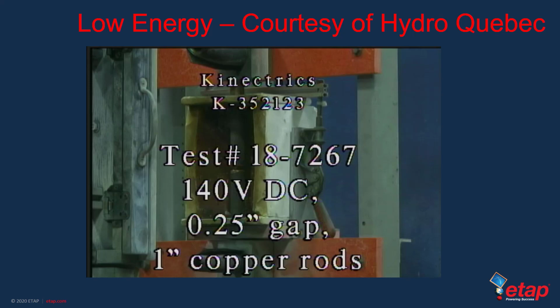The first test is for a 7.8 kiloamp available DC short circuit current system. The initial gap in this system is 6 millimeters, although of course the gap will grow depending on the erosion rate of the copper butted electrodes that we have inside this box. The incident energy measured is about 1.7 calories per centimeter squared. The amount of short circuit current is about 8 times more than what was available in the previous photovoltaic arc flash event videos that we saw.